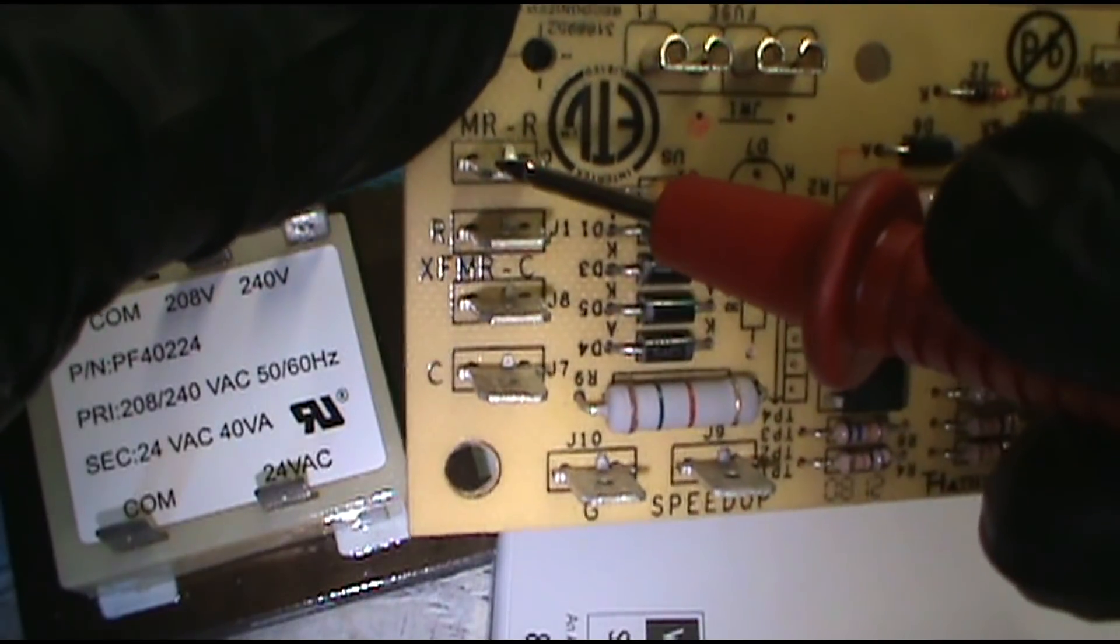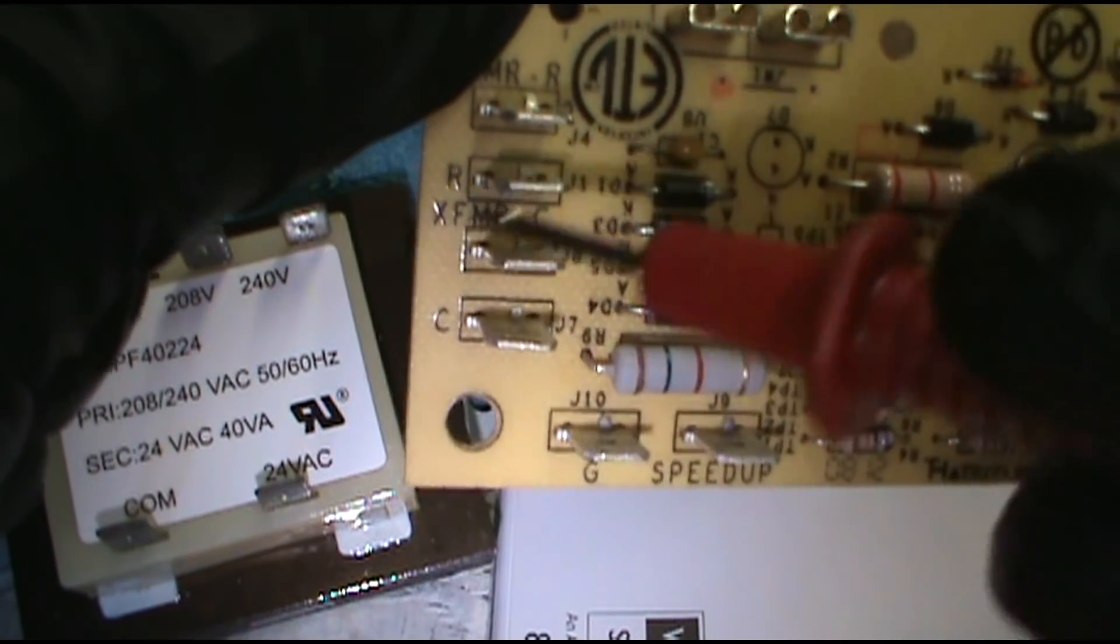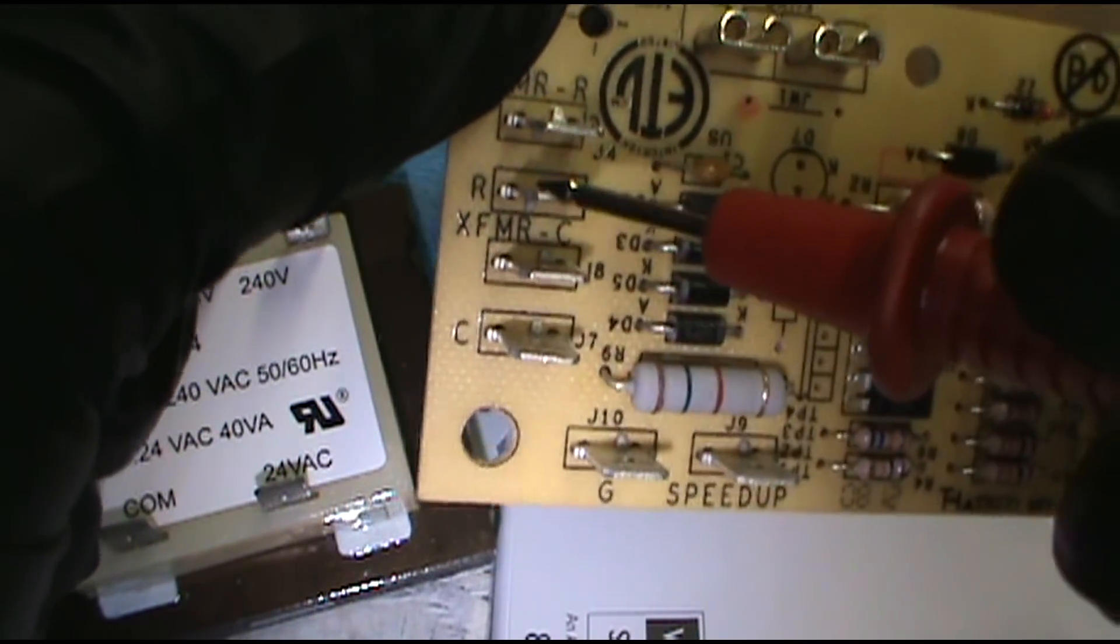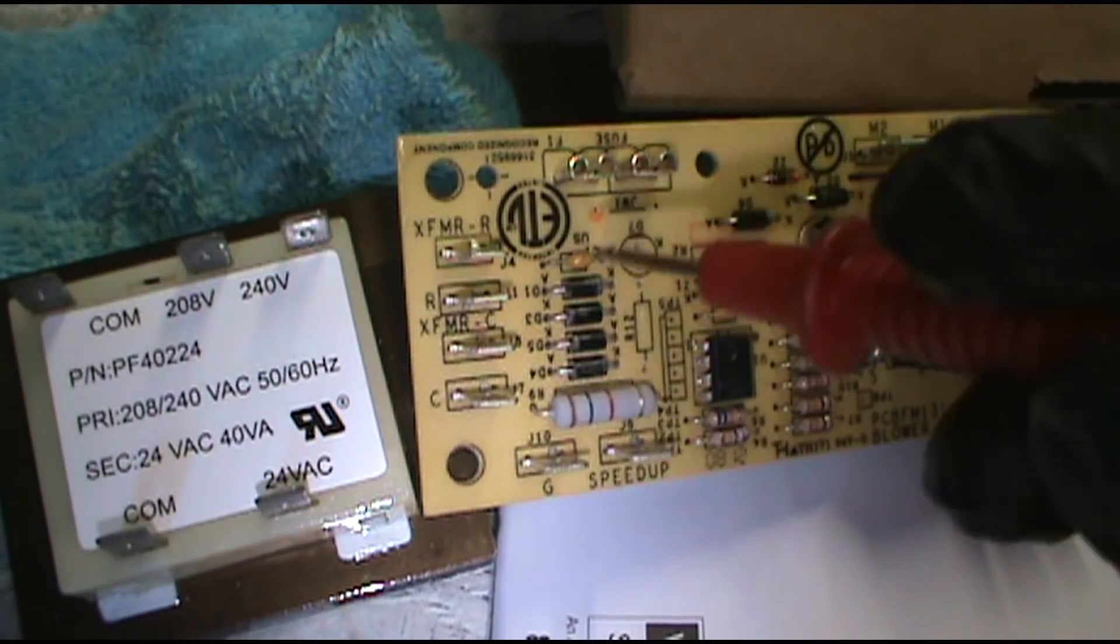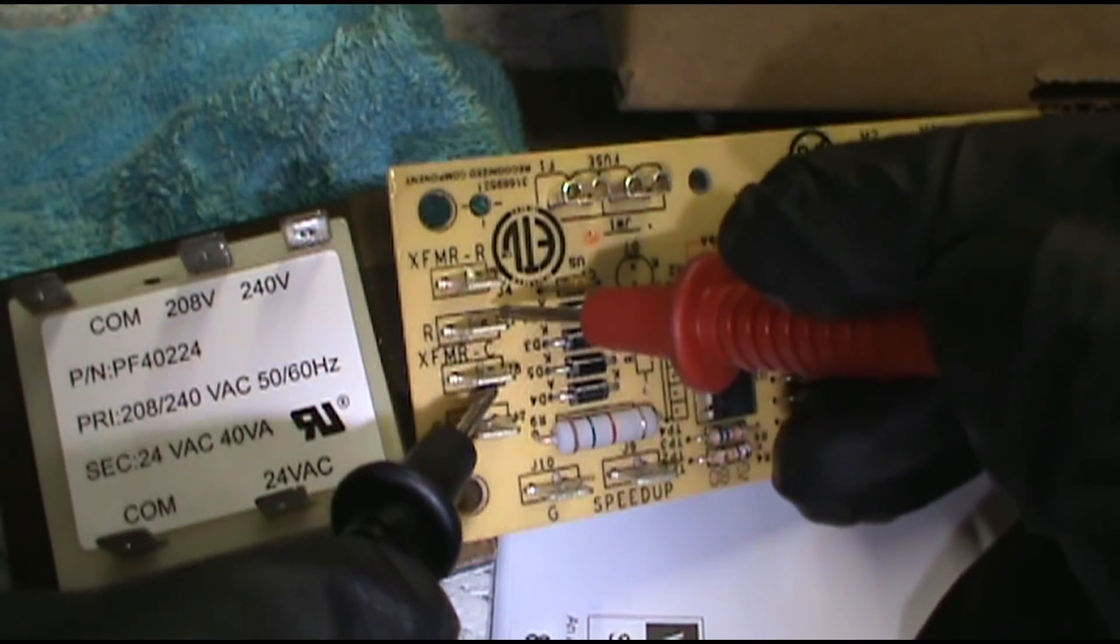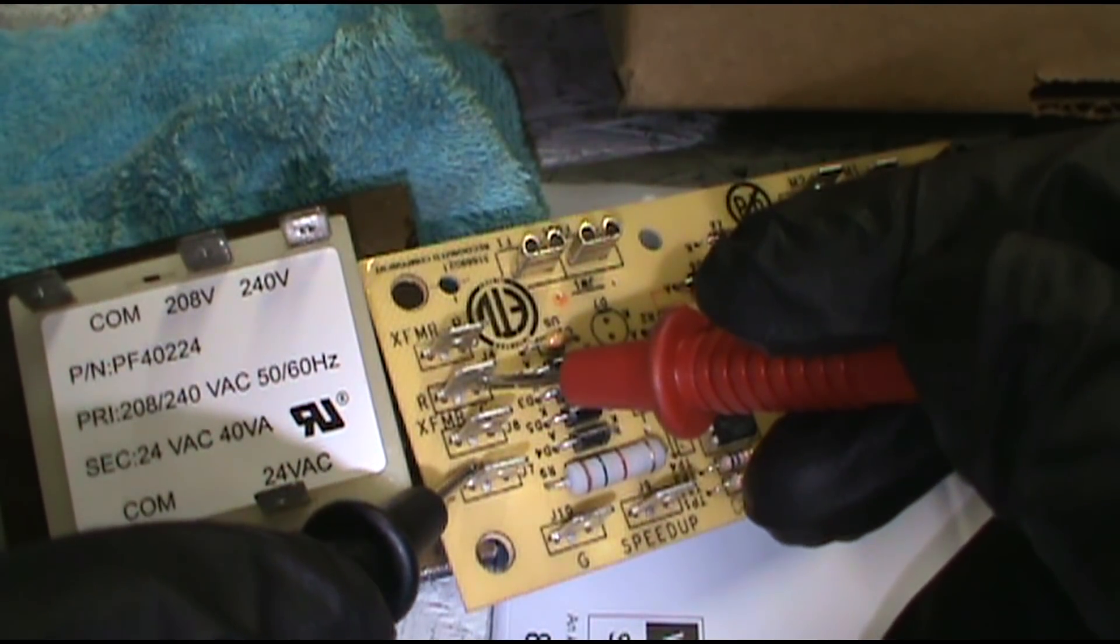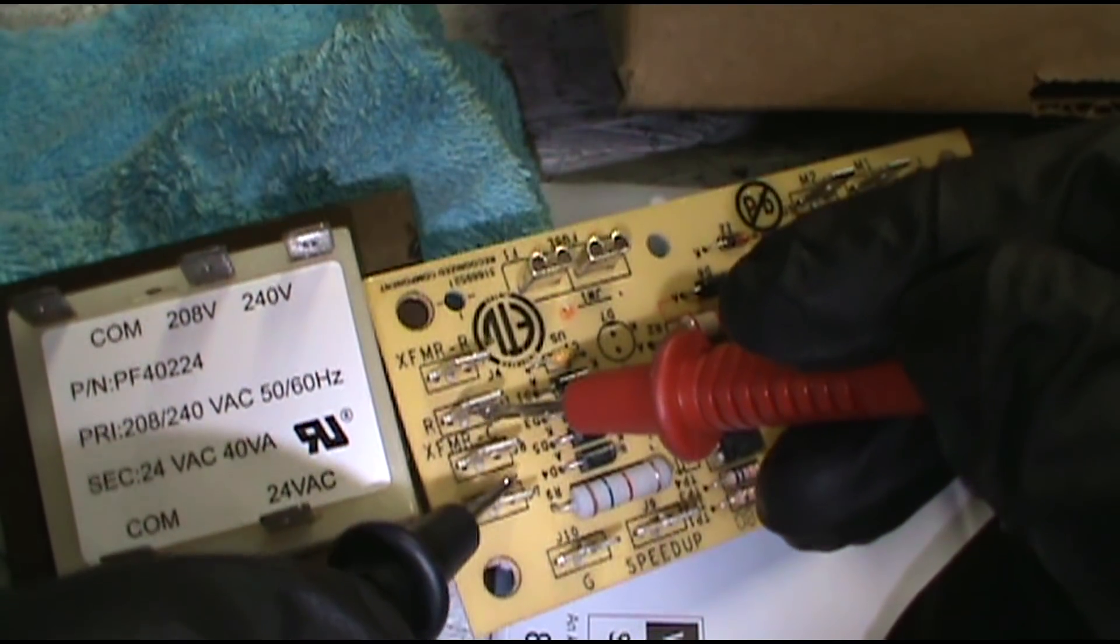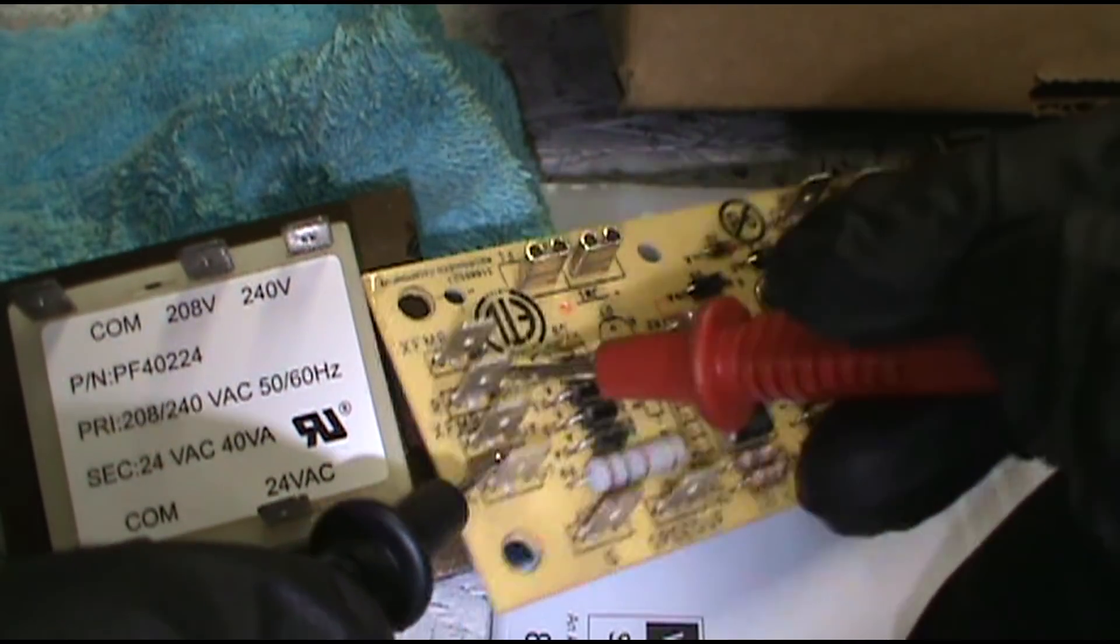What you want to do is test here, make sure you have power coming out. You pull the wires off and you can touch here and here with your voltmeter just like this. Now you're gonna have to do this with the electricity on, so be careful. It's like a deadly game of that board game Operation. Touch R and C, and if you don't have 24 coming out of these terminals, you're gonna need to replace the board. And you can also do continuity as well, and I'll show you.